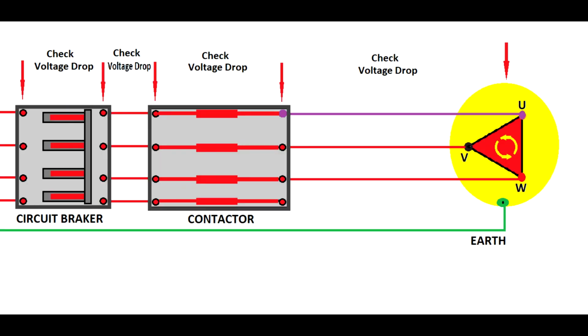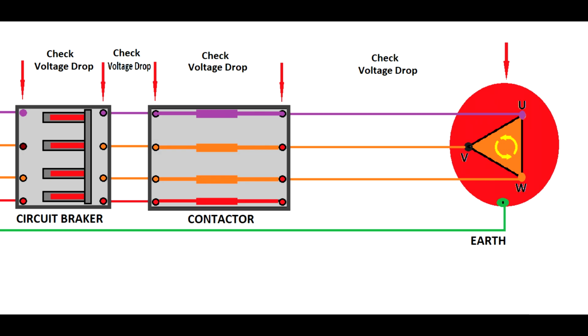Let's see what happens inside the contactor, so we have a clearer view of the potential faults. So let's say we have a voltage drop. Look, here it is between the contactor and the motor, or maybe inside the contactor the blade is damaged. So maybe the entire blade is damaged inside the contactor. Then you convert the electricity into heat, and that will cook the contactor. Or maybe from the circuit breaker to the contactor you have a voltage drop because of a loose connection on the wires. If you have one phase that loses its voltage, the other two phases will struggle, and the running amps will increase until the point where the circuit breaker trips. But by the time the circuit breaker trips, your motor might be burned.